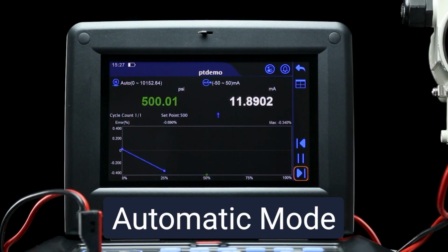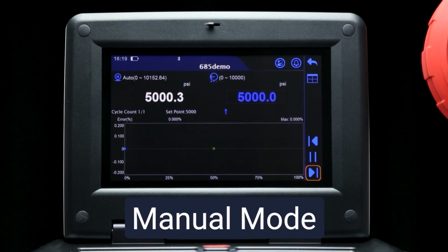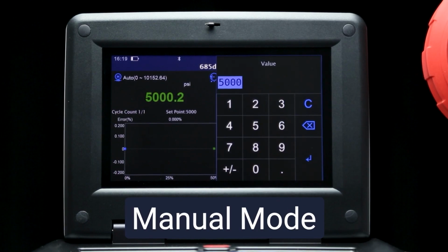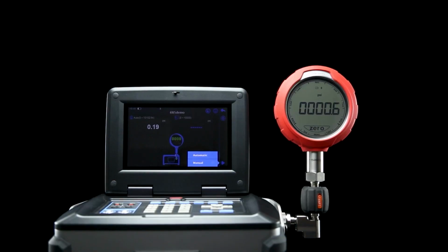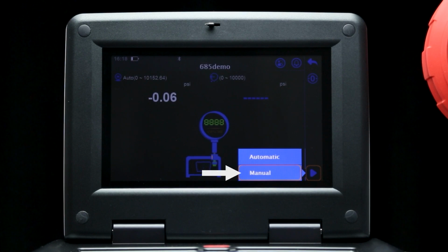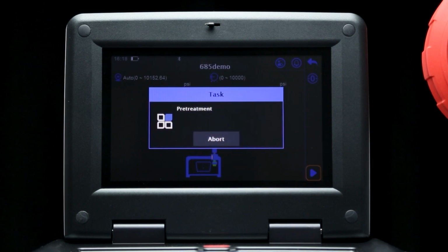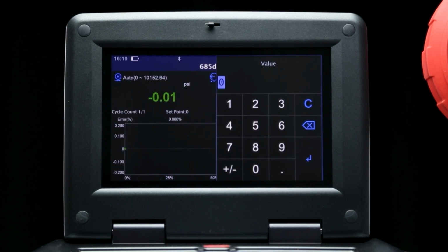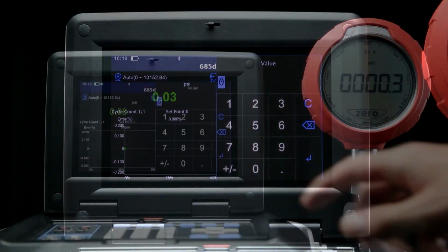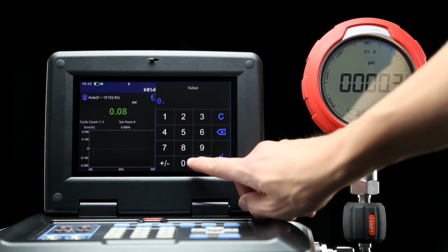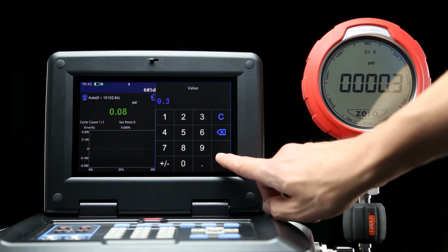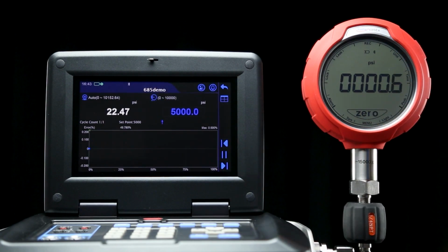Automatic mode will stay at each pressure point for the amount of seconds set in the dwell time, while manual mode will wait for a user to enter data before moving to the next set point. Since the digital gauge has no way to send a pressure signal to the calibrator, we will select the manual mode. After that, the task will begin, prompting you to enter the reading shown on the digital pressure gauge, starting with the 0 point. Once you confirm the reading and press the enter button, the 685 will automatically move to the next set point and provide another prompt.